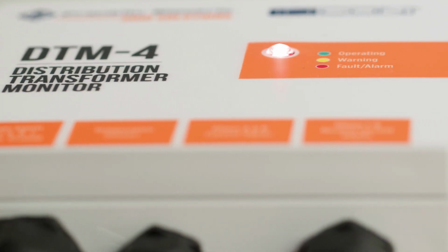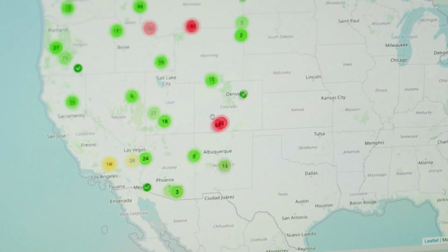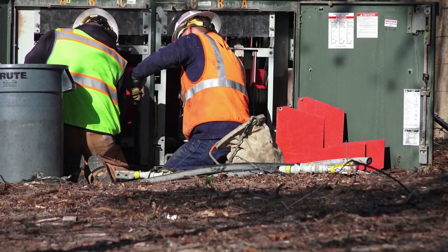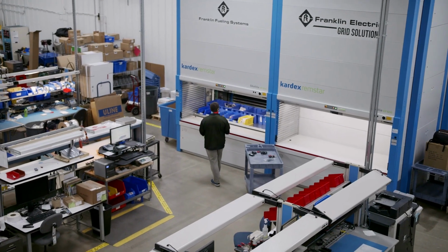That is very important to a utility company because it means that, hey, I know where I'm at with this transformer and I know that it's healthy or I know that it's not so healthy anymore. One of the best pieces of information you can get is real-time alarms. So whether it's fault current, voltage sags and swells, or hot spot temperature changes, all these are alarms that you can use to set and get email notifications of issues that might be pending.